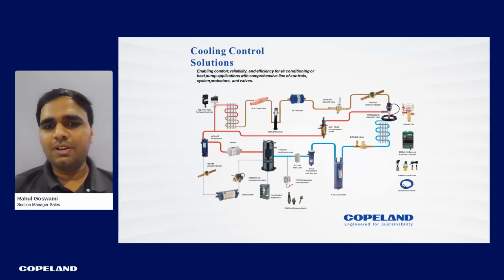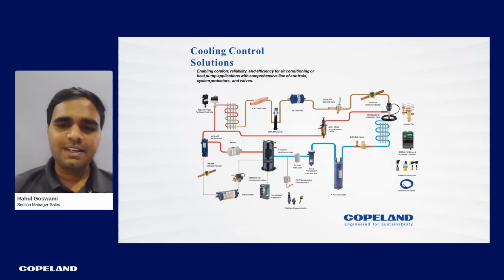Yeah. So you're seeing the basic HVAC and R cycle. As I said, to ensure the optimum performance, you will need a very efficient cooling control solution which will deliver the performance of the machine. Right in the middle, you can see the compressors. Apart from the compressor, we have the mufflers, which are used as a pulsation dampener for the pulsation coming from the discharge line of the compressor. And then we have oil separators, which are used for separating the oil from the refrigerant and sending it back to the compressors, because oil is required in the compressor to work properly.